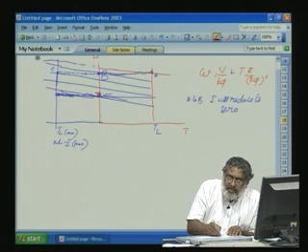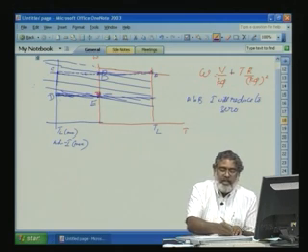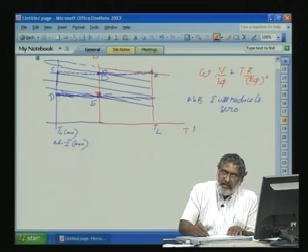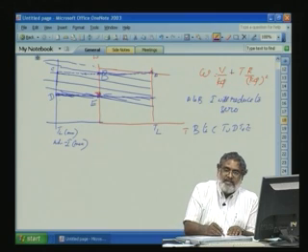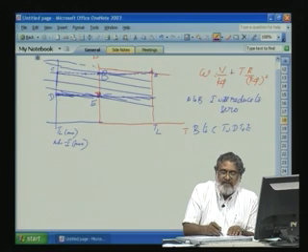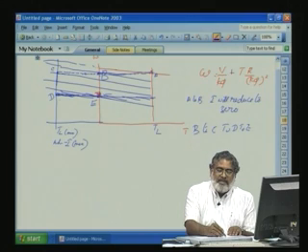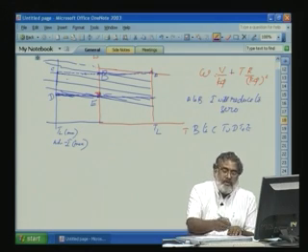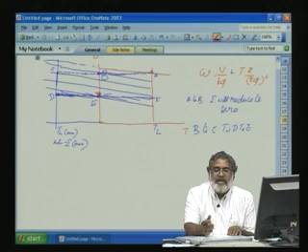That means it will go through various parallel paths. Okay. So, B, C, D, E, that is during the path through B, C, C to D, D to E. That means B to C to D to E, it will be regenerating. From here onwards, current will increase in the positive direction, the machine will give drive power, and the machine will quickly come to this region. So, A to B current decreases, B to C is the electrical time constant. Then from C to D it is a slow process, that is the mechanical time constant, and the machine has come to the required speed. Then from D to E, E to F, we are adjusting the current.